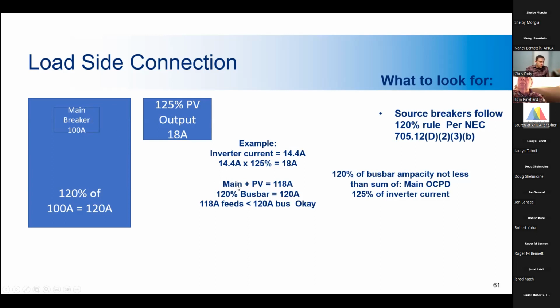So you look at the main breaker plus the PV breaker, that comes to 118 amps, and the bus bar is 100, a 100 amp bus bar. So because it's not over 120% of that bus bar rating, this is okay. And like I said, it's important to make sure that the breaker is at the bottom of the panel, to make sure that at no point in the bus bar is it above the rating of that bus bar.